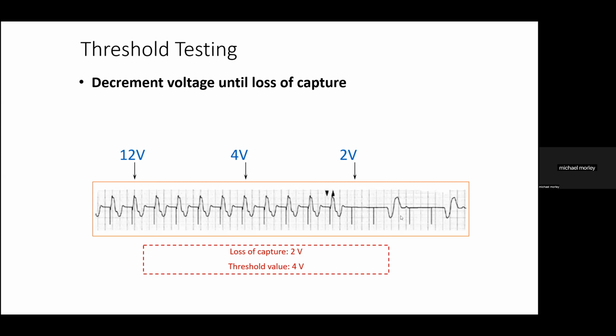Later on in the tracing, you see an escape beat, which is fortunate. And the threshold is defined as the last energy value that actually reliably captured the ventricle. And so in this case, since we went down from 12 to 4 to 2, the last successful energy was at 4 volts. And so that's our threshold. So then we know that we need to set our output higher than 4 volts to ensure that we're getting capture. And so in pacing, we tend to go for twice the threshold as a minimum output. So we might turn the knob up to 8 volts.